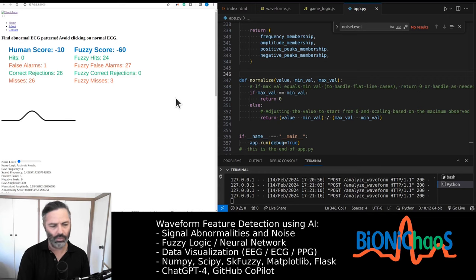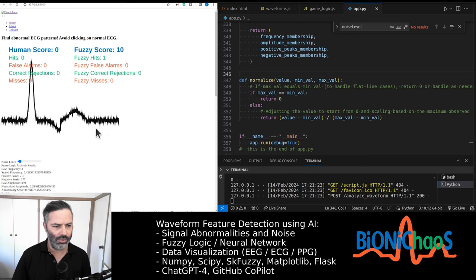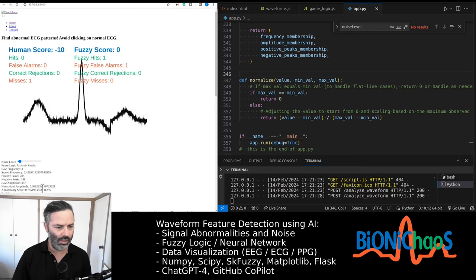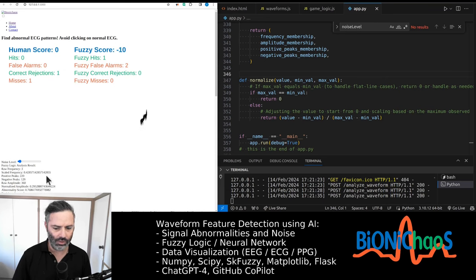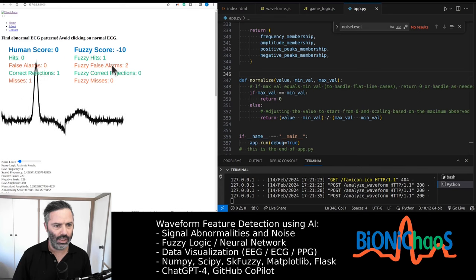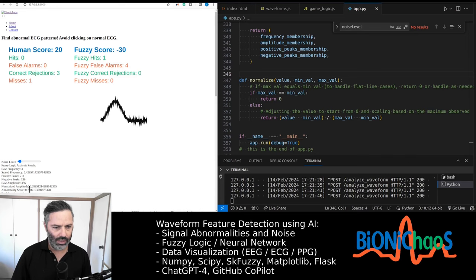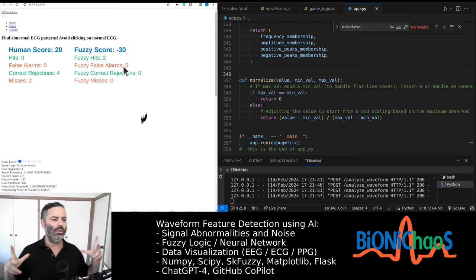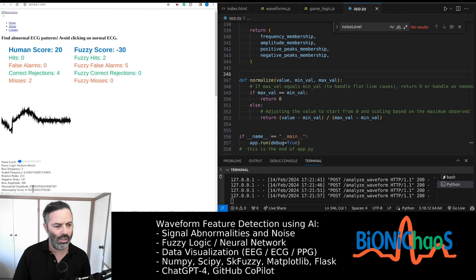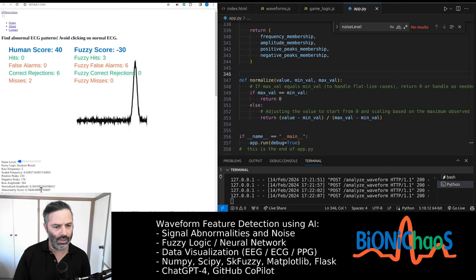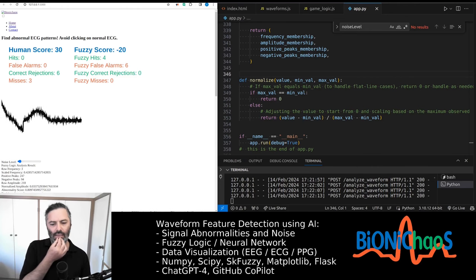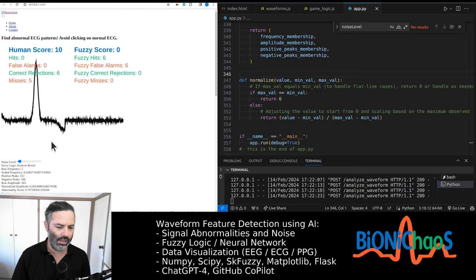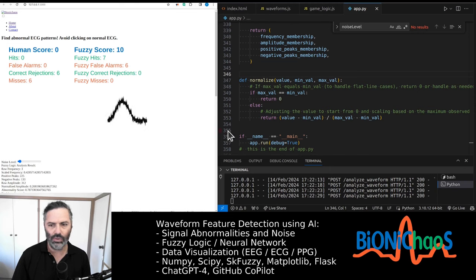Let's start it over again. We have this minimal noise on the ECG waveform we get 0.7 for abnormal wave and 0.7 for a normal one so we still get a false alarm. It's really not doing well with the noise. I keep getting false alarm so essentially labeling normal waveform as abnormal that's no good. I assume this is the noise throwing the algorithm off.